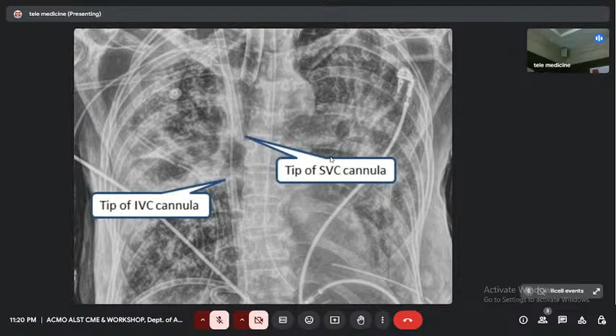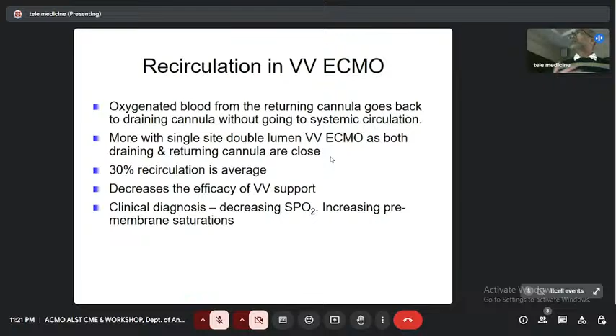So you have to keep these things in check, because sometimes the nurses change the position of the patient. They might do a head up, or the patient has passed stool and is having a wash. In these situations the cannulas can migrate, because the negative pressure in these cannulas because of the pump is so huge that you shouldn't assume the cannulas won't migrate even after 5 or 7 days. They can migrate. So these are things which we have to check on a regular basis. Similarly, there's something called Harlequin syndrome, where you start a patient on VA ECMO. This is the peripheral VA ECMO. And when the return, sorry, I'll just show you this.